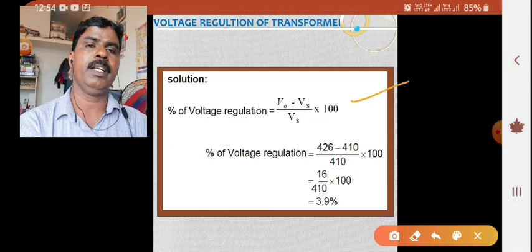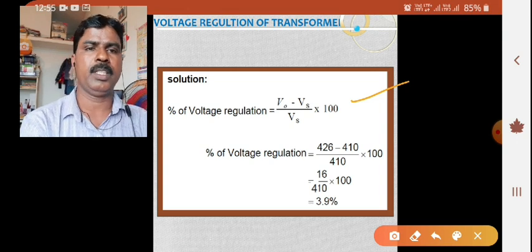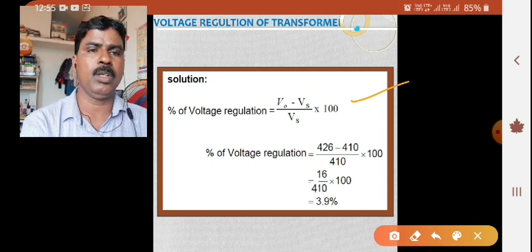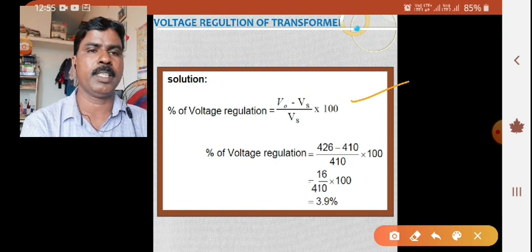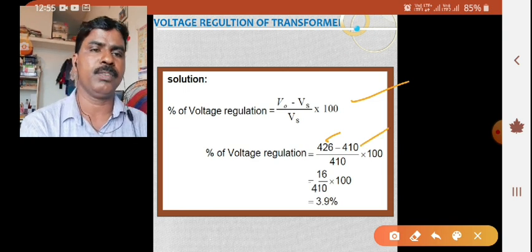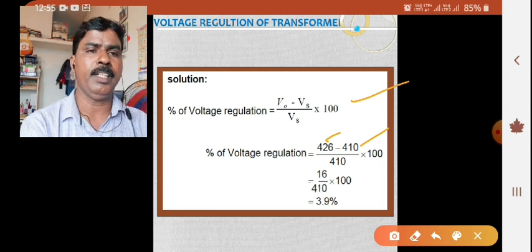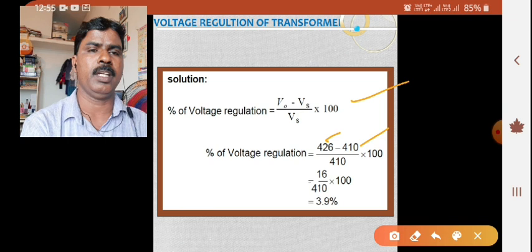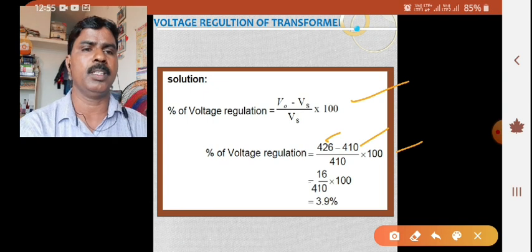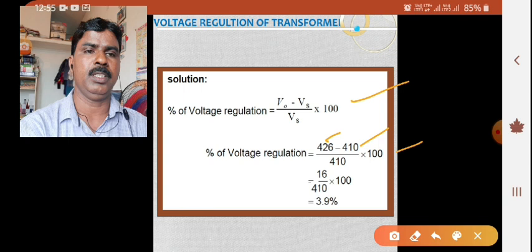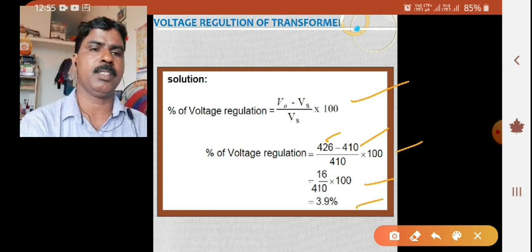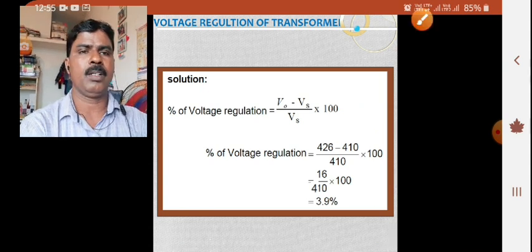Applying the formula: percentage voltage regulation equals V-0 minus V-s divided by V-s, multiplied by 100. Here, the no-load secondary terminal voltage V-0 is 426 volts, and the full-load secondary terminal voltage V-s is 410 volts at 0.92 power factor. So, percentage voltage regulation equals 426 minus 410, divided by 410, multiplied by 100, which equals 16 divided by 410 into 100, giving 3.9 percent.